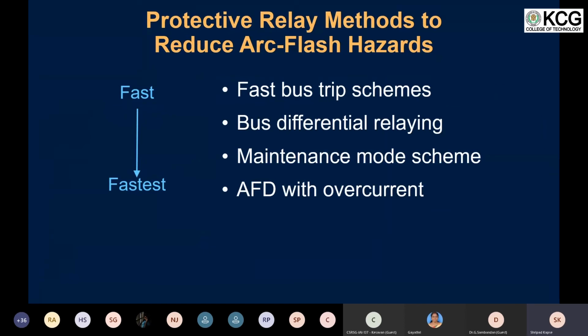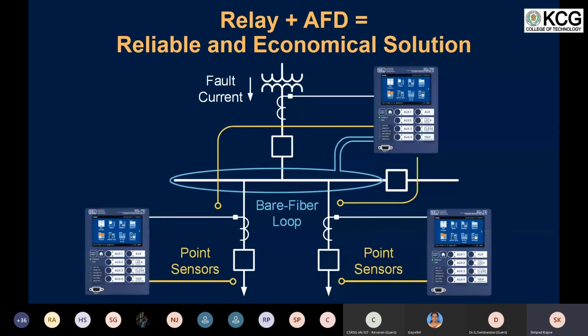So even from the reliability point of view and the operating time point of view, relay-based arc flash protection is going to offer you a much better, faster and more reliable solution. In this case, what we generally do is we use the same relay which is used for protecting the incomers and the outgoing. The same relay is connected with a few sensors.